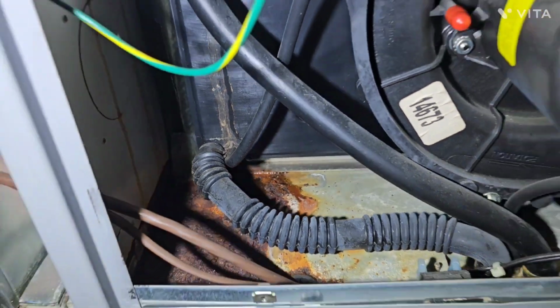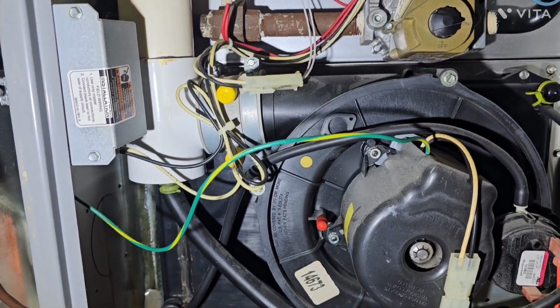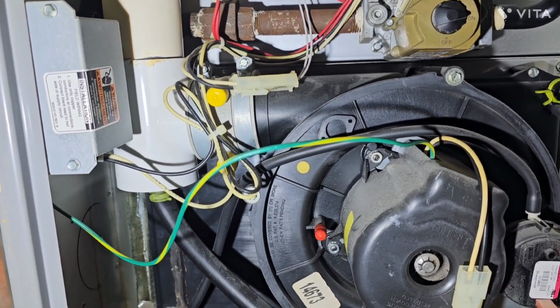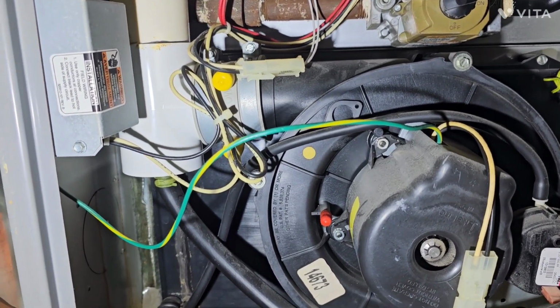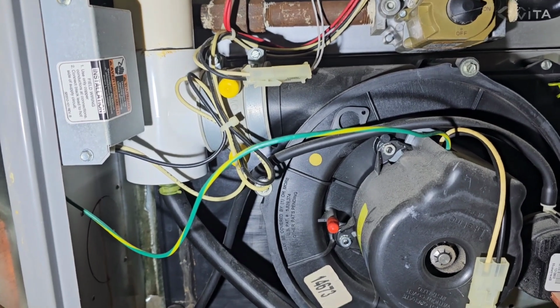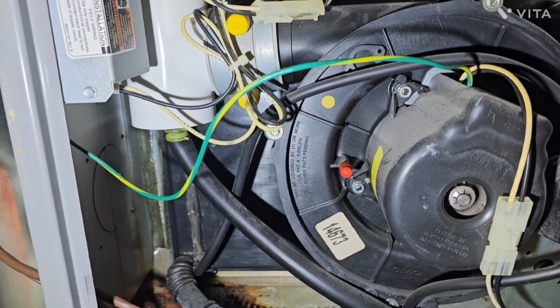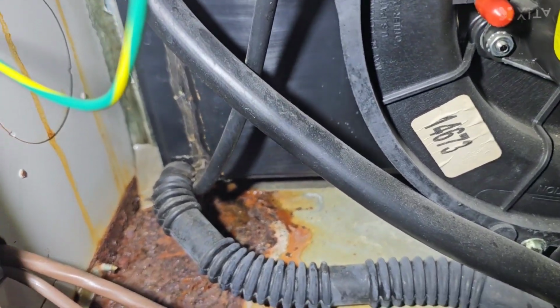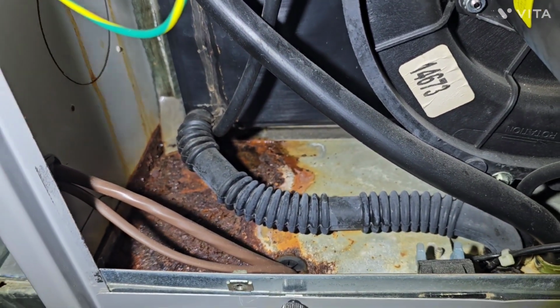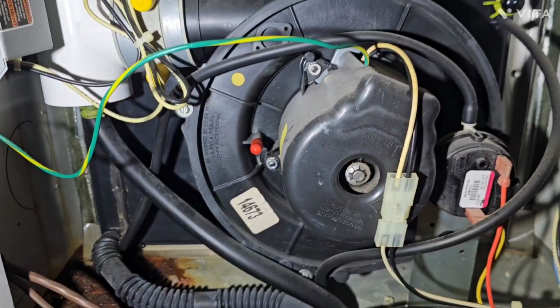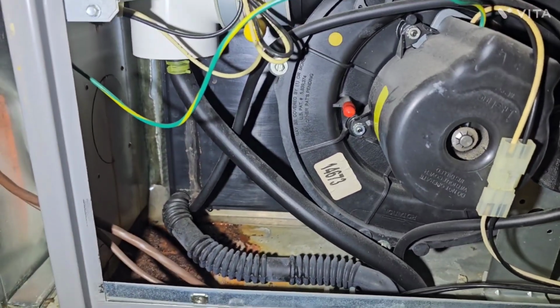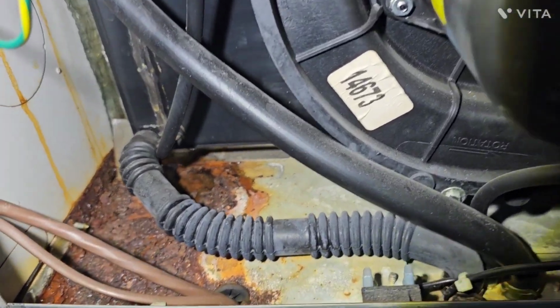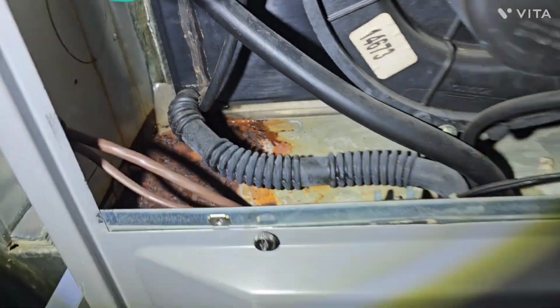Normally it wouldn't be a big problem, except that the condensate that's being formed is acidic because of the products of combustion. What's in the fuel essentially makes it acidic. It looks clear as a bell, but it is acidic, and when it lands on the metal it does this. And if you don't catch it in time, it can do different things. It can build up into the fan, it can shut your furnace down as a result of that, or it can just rust out the cabinet.